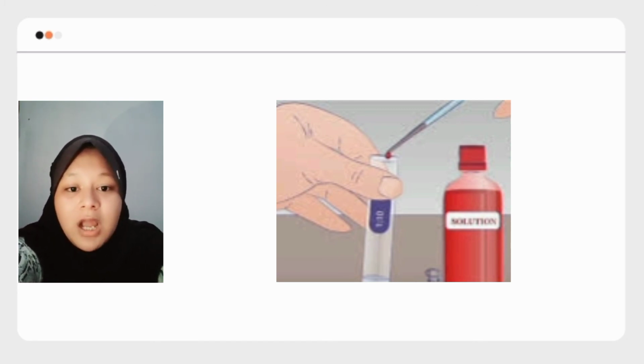C. After the cuvette containing the blank solution is in position, set the colorimeter pointer to the number 0. D. Discard the blank solution, rinse the cuvette with the control solution, add the control solution into the cuvette, insert it into the colorimeter and read the absorbance of the solution R.